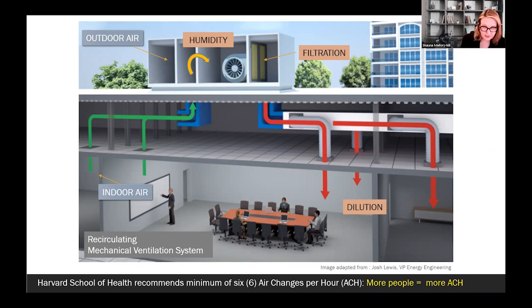In the coldest and, again, the hottest times of the year, the percentage of outdoor air is reduced, because the air handling units can't handle extreme temperatures. They freeze up and get locked out. So in some cases, the outdoor air contribution can be under 10%, but standards say you need to have at least 15 cubic feet of outdoor air per person.